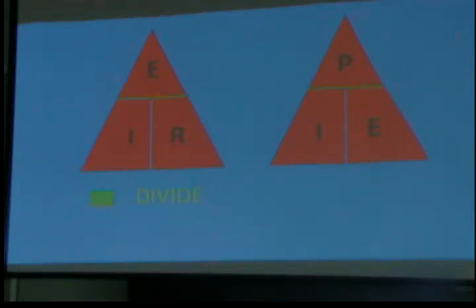How are these important? They are important because they are relationships when you're working with electricity. I'll give you an example. You have a 1200 watt heater. You know those little ones that you get around the house? They're 1200 watts. How many amps is that thing going to draw? It isn't marked on the heater in most cases. But if you take 1200 as the power, you take 120 as the voltage, and you divide 120 into 1200, what do you get? 10.